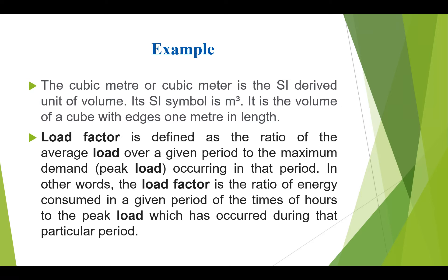The load factor is the ratio of the energy consumed in a given period to the peak load which occurred during that particular period. In other words, it is the average load divided by the peak load. It can be a monthly, daily, or yearly load factor depending on the duration of time considered.